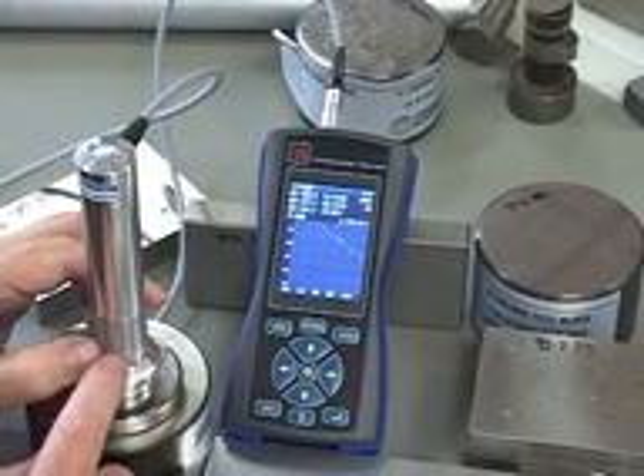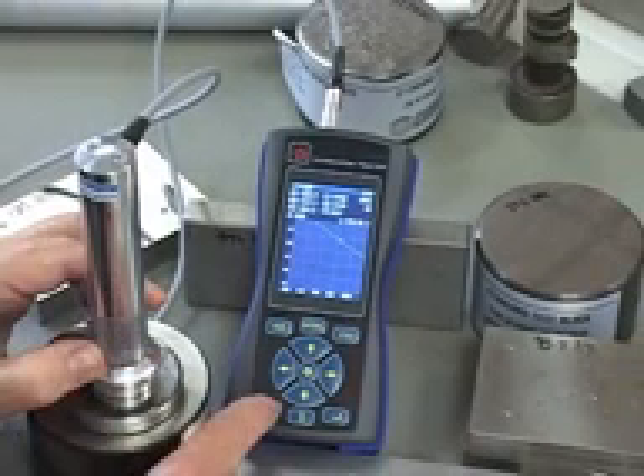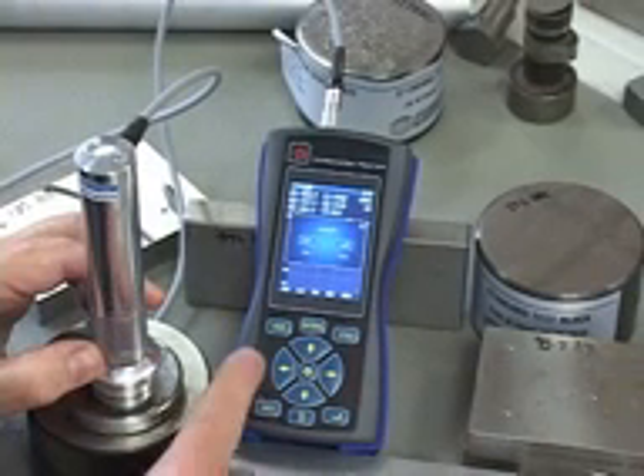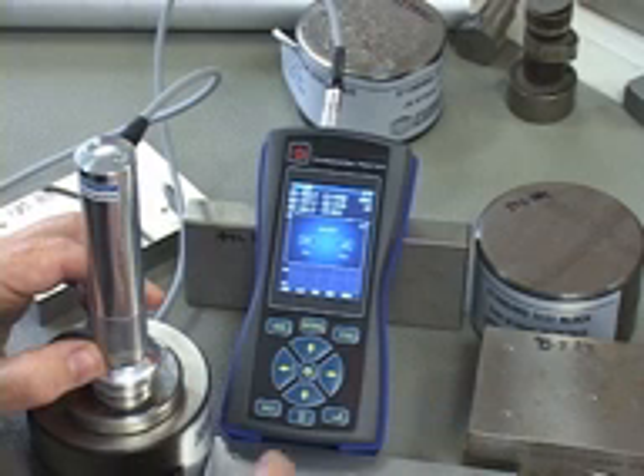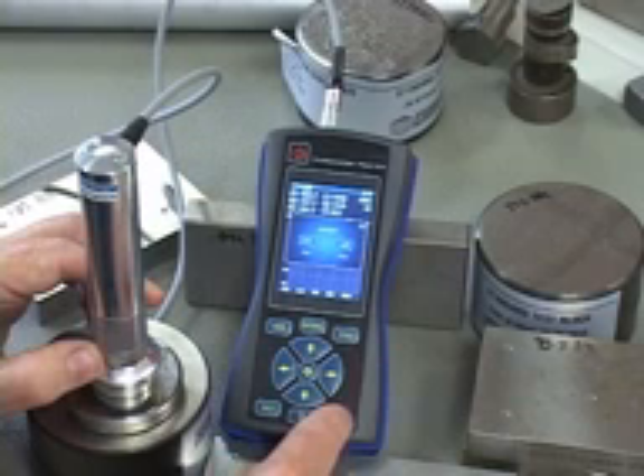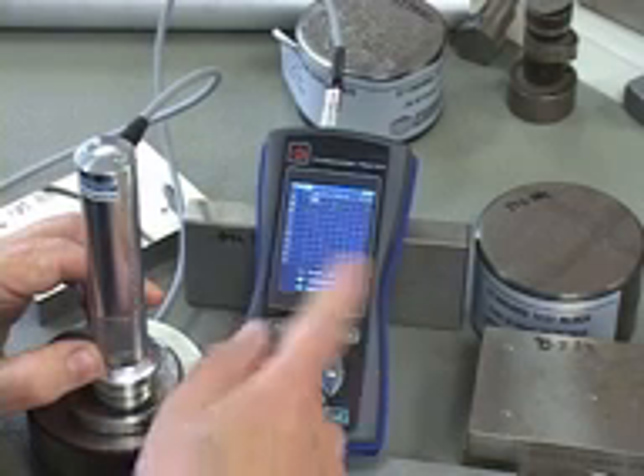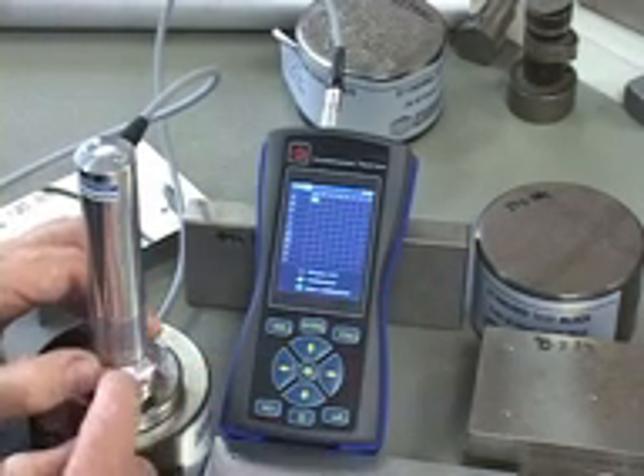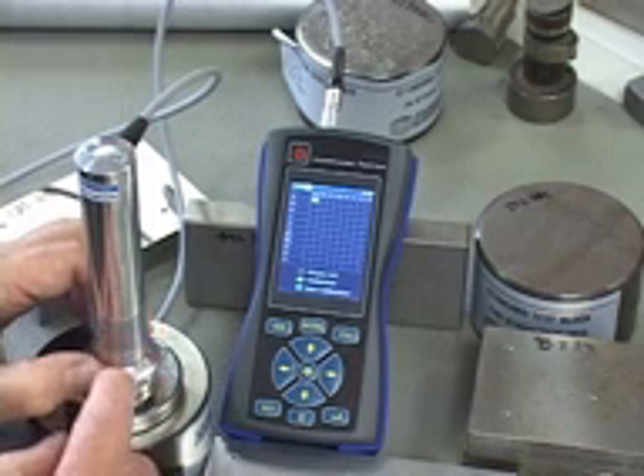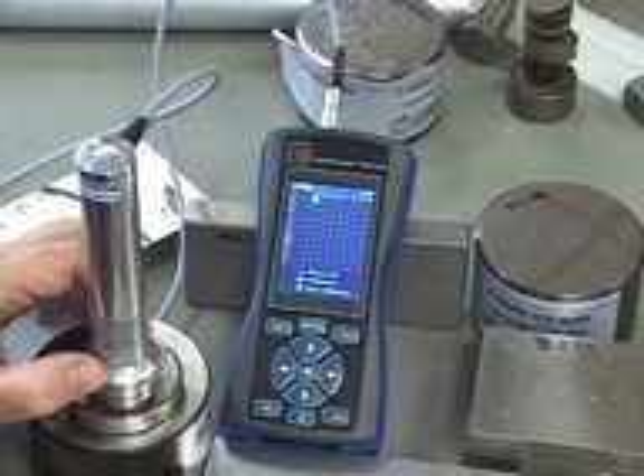To store this in the device, in the memory of the probe itself, I hit the backspace button, and it comes up and says, well, you've done these calibrations, do you want to save it? No would be hit the back button here, or as the icon shows, yes is to save it. So now it's display scrolls. I've now calibrated this test probe for that material, steel, for those 3 test blocks.